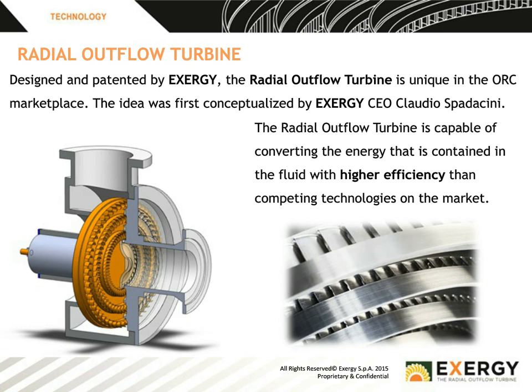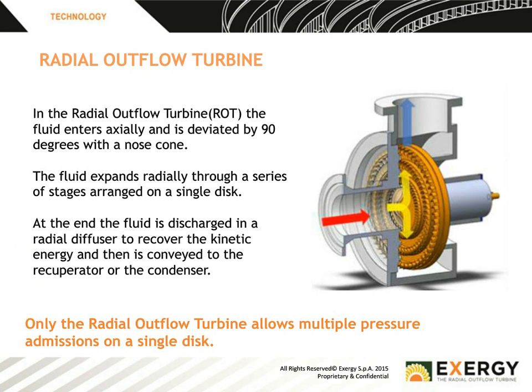However, we are able to have an overall cycle design which gives us a higher efficiency than our competitors due to this innovative idea regarding the turbine. And this is the Radial Outflow Turbine. So if we move on to how the Radial Outflow Turbine works, you've got the red arrow here, which shows the axial entry of the fluid into the turbine. We then have yellow arrows, which show the fluid expanding across a stage. And on this particular turbine we have drawn here, this representation of a turbine, you see 3 radial stages. So that means the fluid moves radially outwards, passing through 3 moving radial stages. We can have up to 7 stages on a single disc, but in this case, for the simplification of the drawing, you see just the 3 stages.